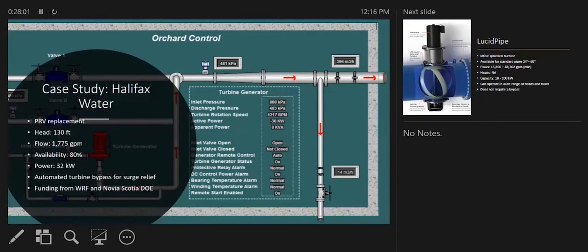One of the really well-publicized cases of replacing a PRV with a turbine is Halifax Water. They did a really good job documenting their whole process of site selection, engineering, and turbine selection. That site had a head of about 130 feet and a flow of 1,700 GPM. Their availability was 80%, and since it had a very steady flow, it was easy to pick a target flow and head, giving a 32 kilowatt capacity based on availability. This design required an automated bypass for surge relief, and I assume also for when they didn't have availability. That project was funded by the Water Research Foundation and the Nova Scotia DOE.